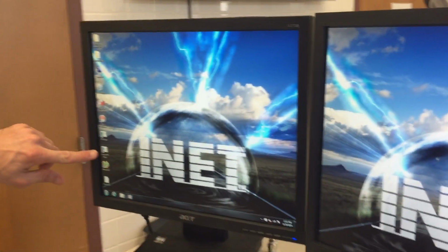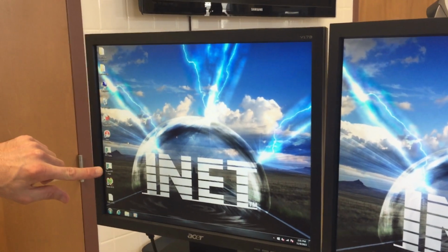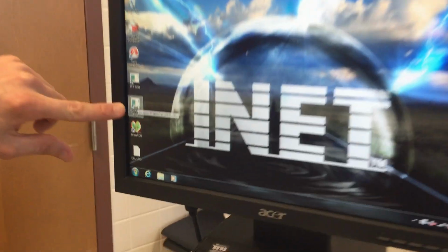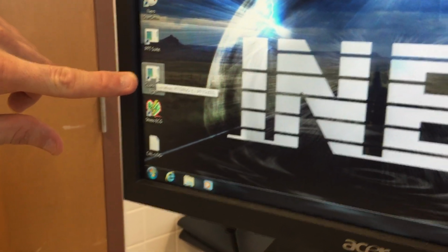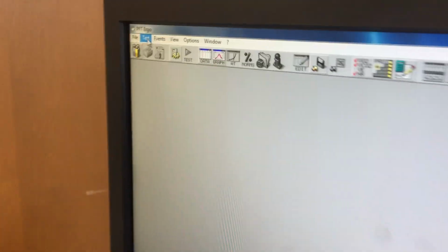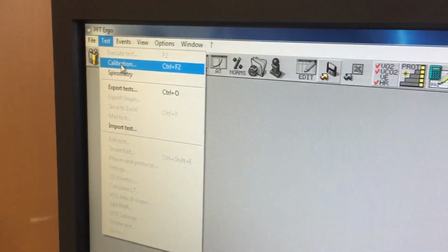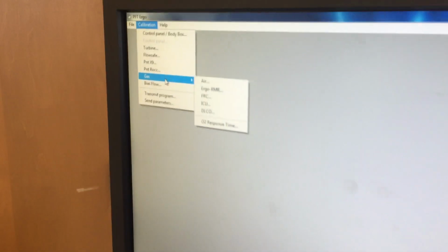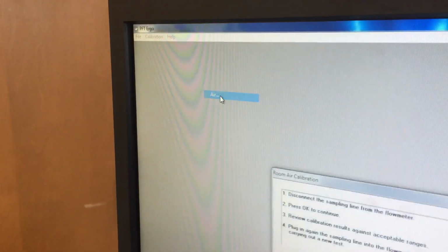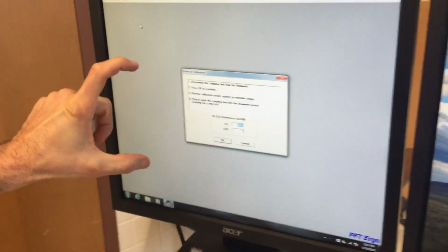Then we can focus on the computer. The icon we're opening up is the Quark PFT Ergo. This is the same icon we use to calibrate and to do the metabolic testing. We double click to open it up. And then the first thing we need to do is go to Test and then Calibration. We click Calibration and a new screen will pop up. We then go to Calibration, Gas, and Air. We click that and we're going to see a little screen pop up.